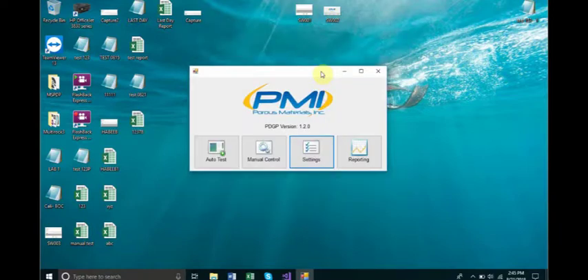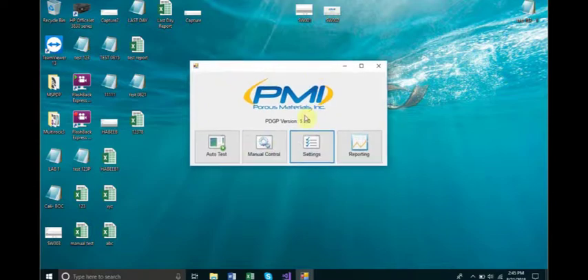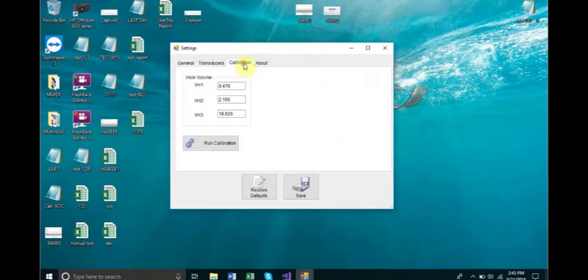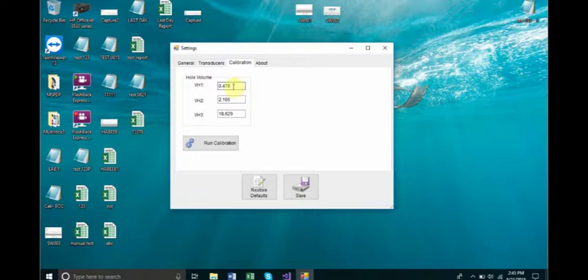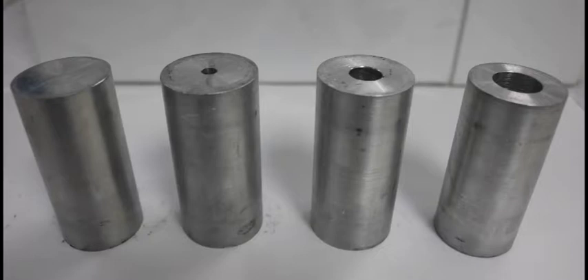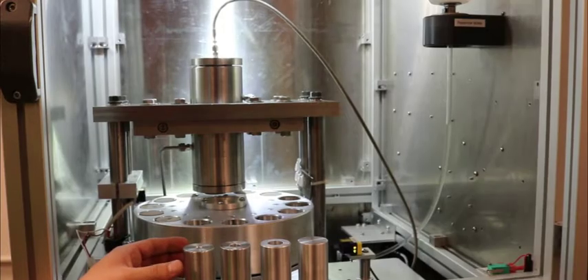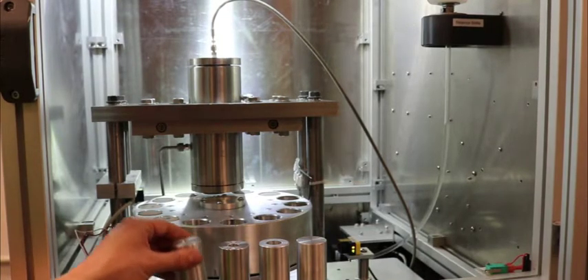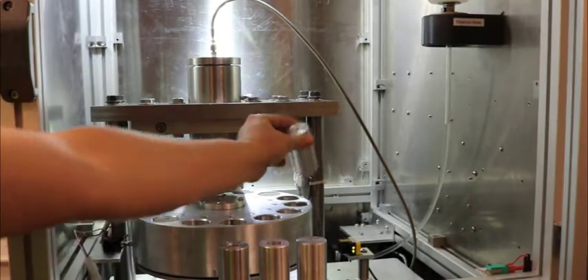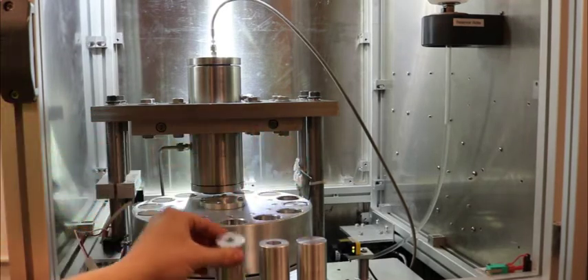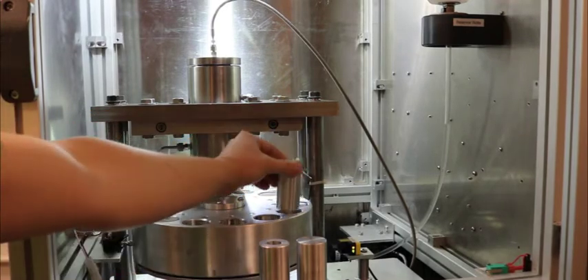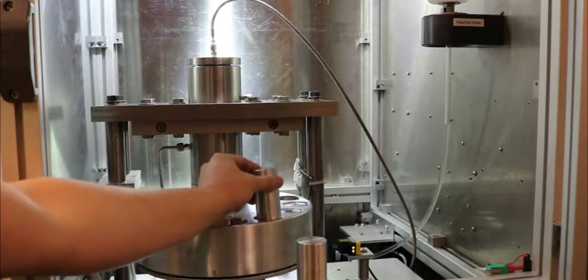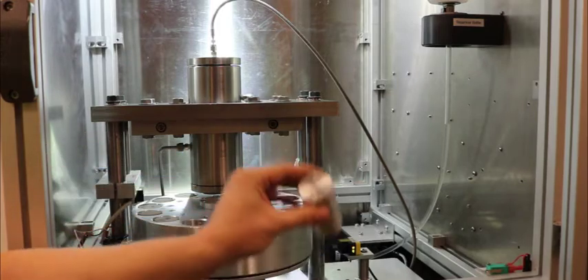Before running its first auto test, your machine will need to be run through a calibration. This will measure system volume and place data into a file which will be crucial for calculation and reporting on actual sample data. To run a calibration, in the settings window, click the calibration tab. Notice the three input fields located in the hole volume panel, VH1, VH2, and VH3. These fields should hold the value for the volume of each corresponding calibration plug included with the APDP-HP101. There is also a solid plug included as a zero-volume standard. Before running a calibration, these four plugs should be inserted into core slots one through four of the carousel. Place them in the slots in order of increasing volume beginning with the plug possessing the smallest diameter hole. Place the plug with no hole last.